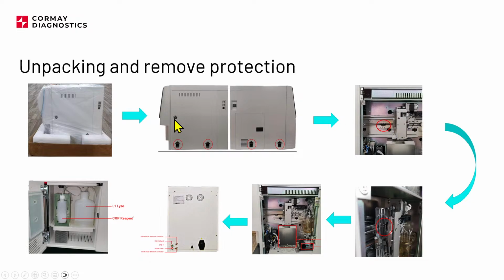Inside of the analyzer, on this side exactly, we have those clips. Those clips need to be removed. One is on the horizontal, and one is keeping the vertical movement of the needle, so the needle will not be damaged during the shipment. You need to remove this. And later you need to check that everything is fine in the impedance channel. You need to make sure that there is no loose tube or anything like that in this area.